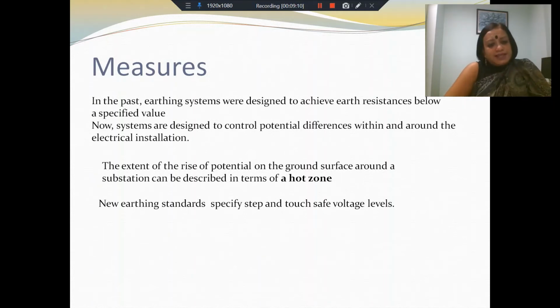The extent of the rise of potential on the ground surface around a substation can be described in terms of a hot zone. So whenever you have an electrical installation, around that there is a zone in which you expect the potential to rise considerably. And we have to look at this hot zone and try and control the EPR within the hot zone. How do we know how much we should allow the potential to increase? There are standards for that. There are earthing standards which specify step and touch voltage levels which are safe for personnel, and there are also other standards which tell us how to deal with this situation.